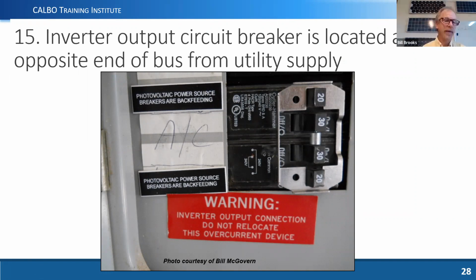However, that being said, with the energy storage projects that are coming down the road, things have changed quite a bit. And if time permits at the end, I'll show you some diagrams that explain those different arrangements that you're going to need to use because of the fact that we're bringing in, especially with AC coupled inverter battery systems, Tesla, Enphase, all these different companies, Franklin is another new company. These companies are doing AC coupled systems. So your AC supply to the bus bars is well in excess of the 120% rule, and so you've got to go about doing it differently.